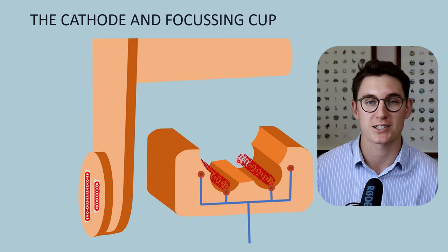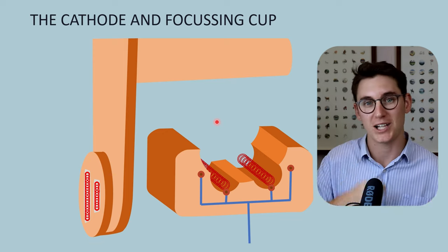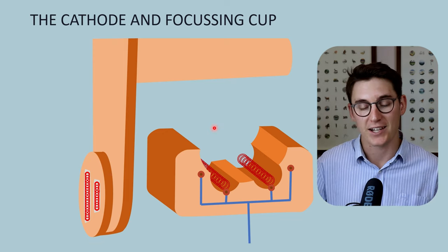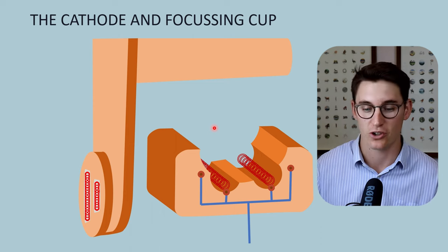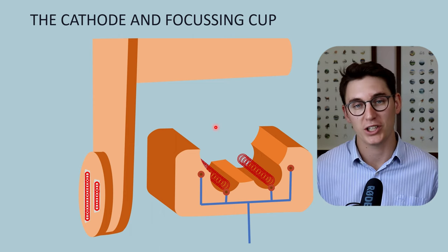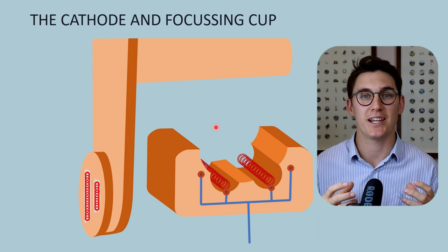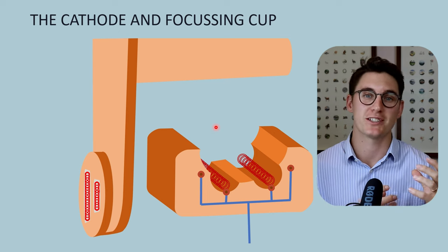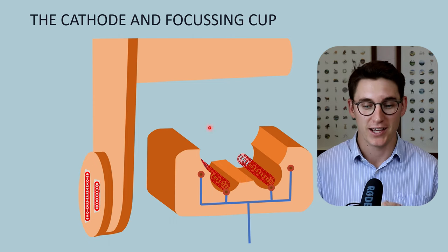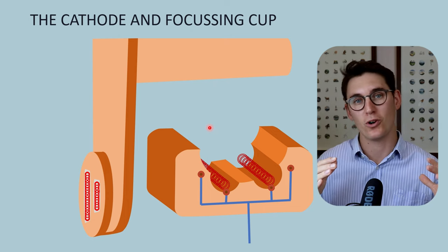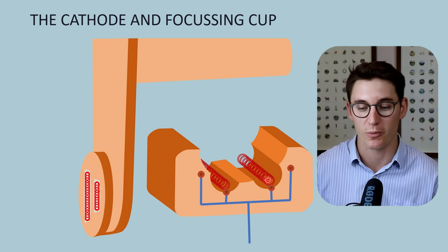Why exactly do we use tungsten for our coil? First, we can machine tungsten into a very thin coil and wrap that coil tightly within the cathode itself. That really thin tungsten will allow for a lot of surface area so we can generate lots of electrons on the surface of the coil. Not only can we machine it into a very thin filament, but tungsten itself has a very high melting point, and because this process requires a lot of heat, we need tungsten to maintain its structural integrity at high temperatures. Lastly, tungsten has a high atomic number with lots of valence electrons, making it a good thermionic emitter.